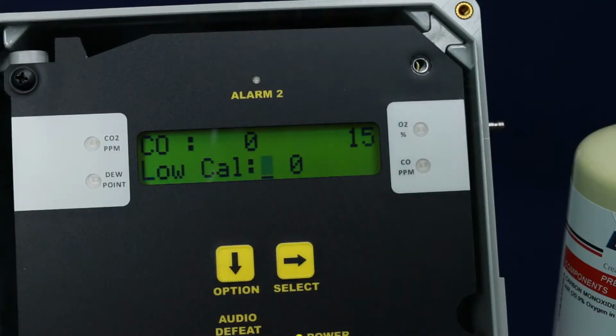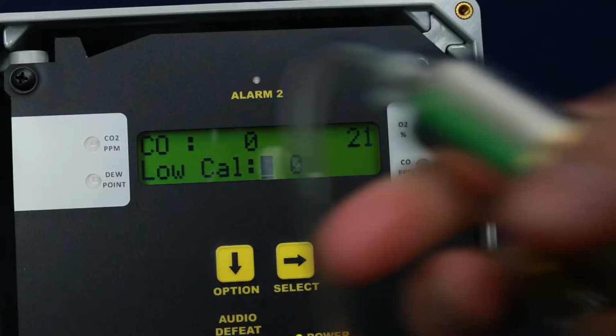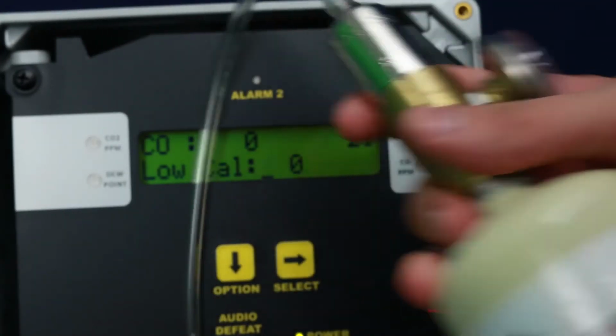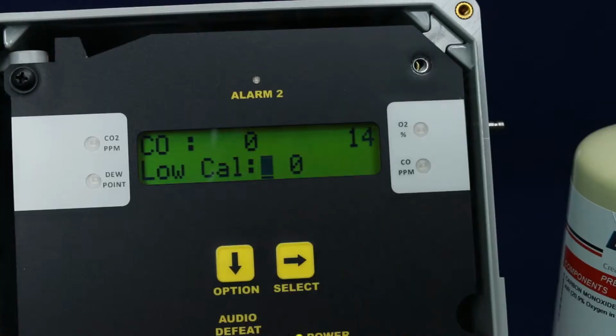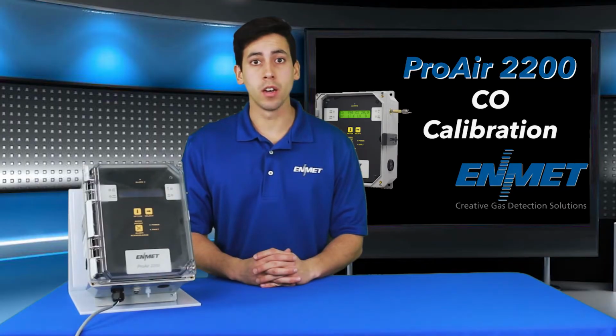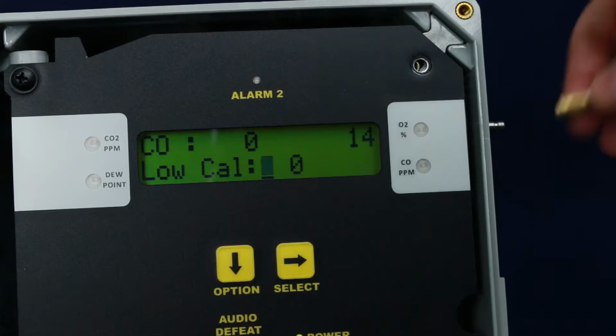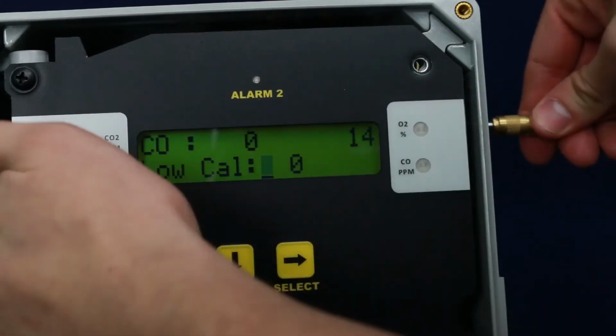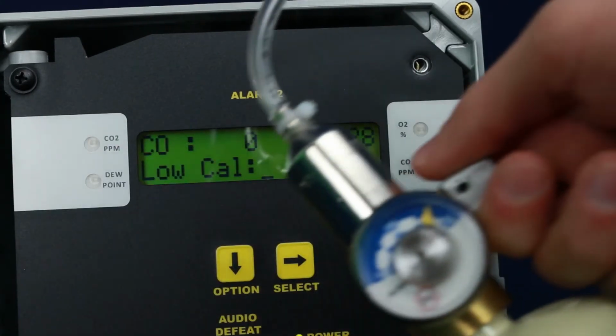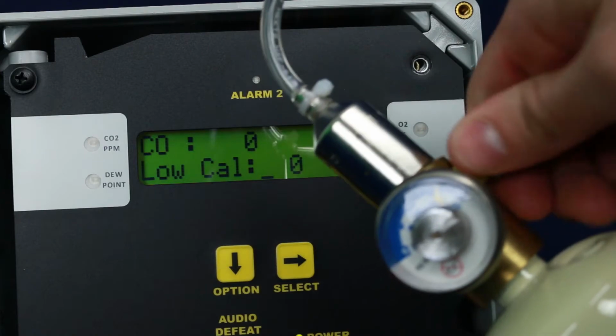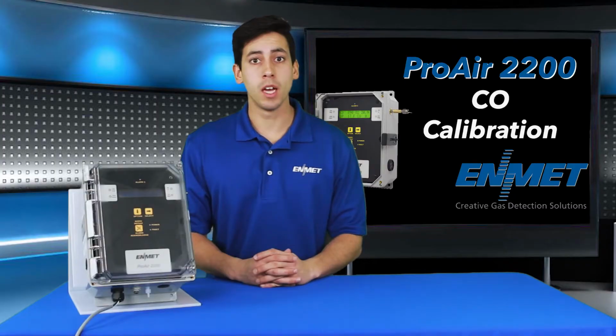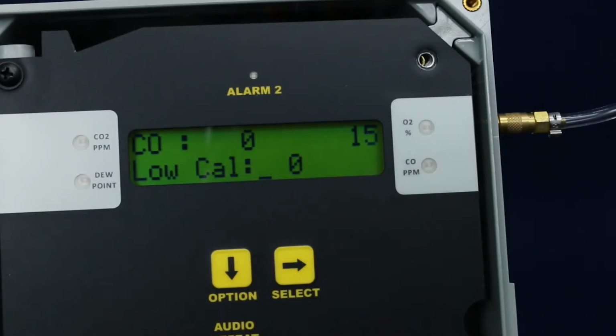At this time, you will attach the 20.9% oxygen zero gas or your clean compressed air supply to the calibration regulator assembly, and then connect the regulator to the instrument inlet. Open the valve on the regulator to apply clean air. After doing so, allow the signal to stabilize for at least 90 seconds. A small amount of movement in the sensor signal is normal.